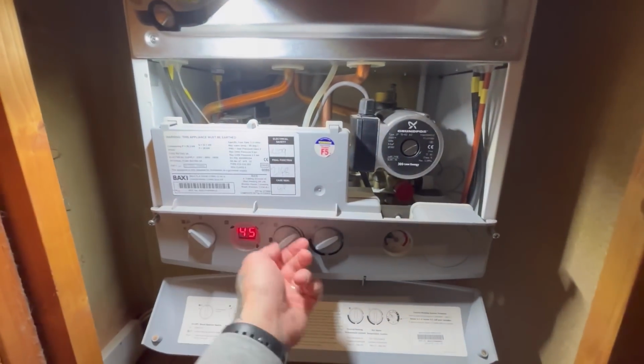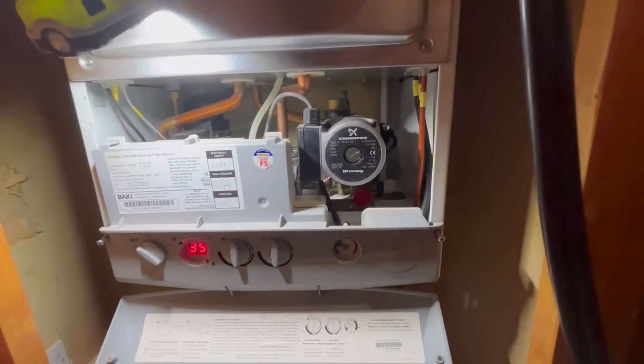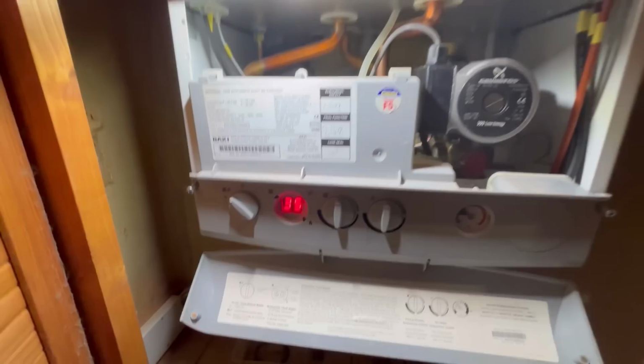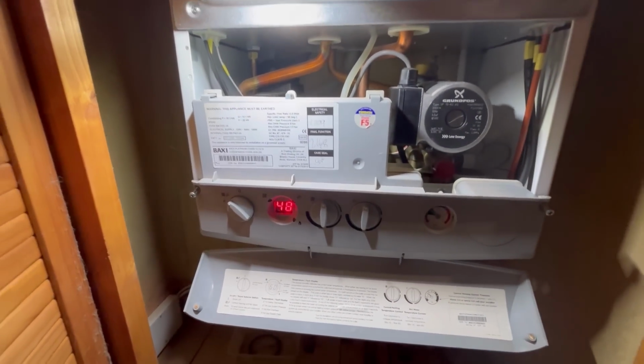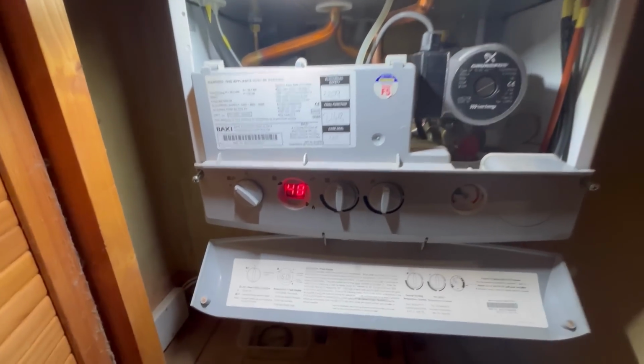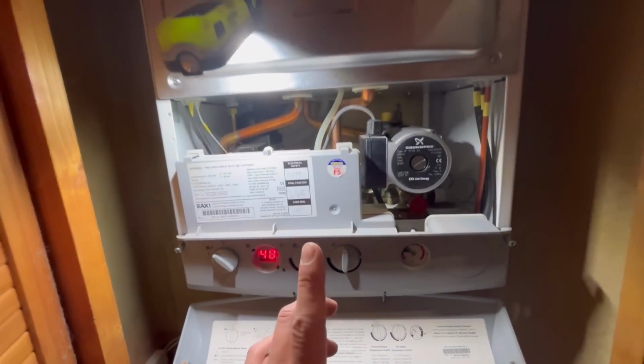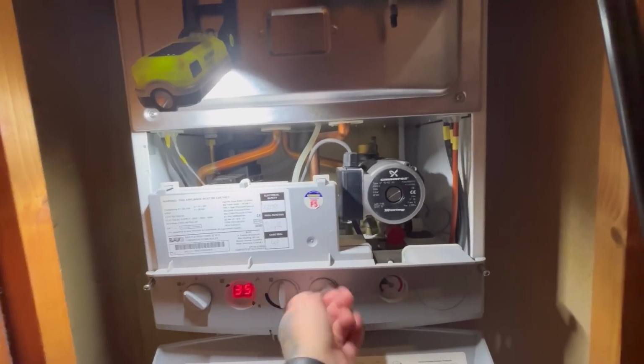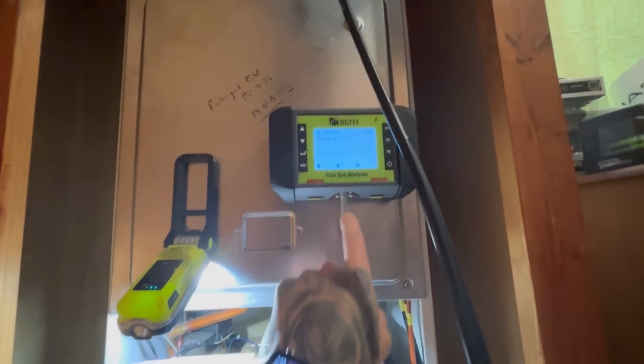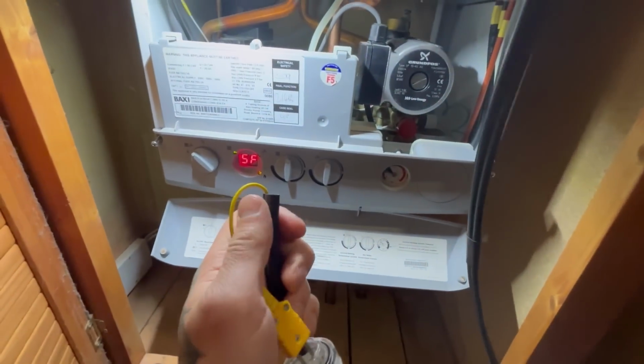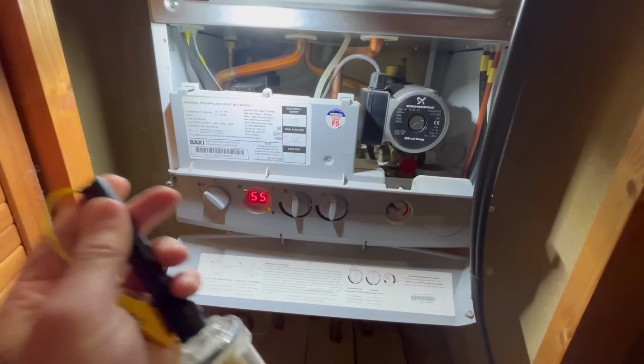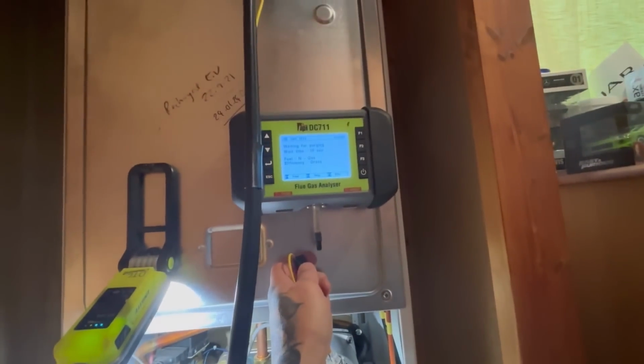So this boiler I serviced only a couple of weeks ago, and after half an hour of the heating running now, it's making a horrendous noise. It sounds very much similar to an Ideal Logic. I'll see if I can try and get it to make that noise, but I'm just flicking the analyzer on. I'm just going to double check our minimum readings, because obviously after half an hour of the heating being on, it'll be looking to modulate down and the gas valve will go to minimum. So I want to check that that is within tolerance first.